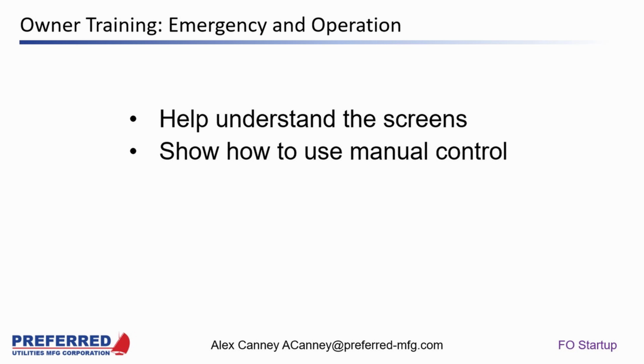Also, from a preferred standpoint, all of our pump set panels are designed such that if the PLC fails, you still have manual control of those pumps. So you can get a level or a day tank filled by putting the pump in hand. That's a really good point, Don.